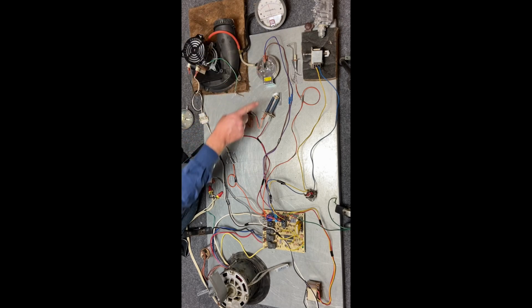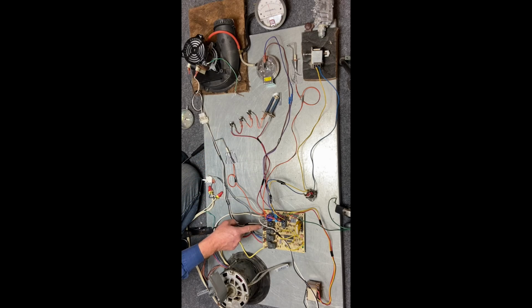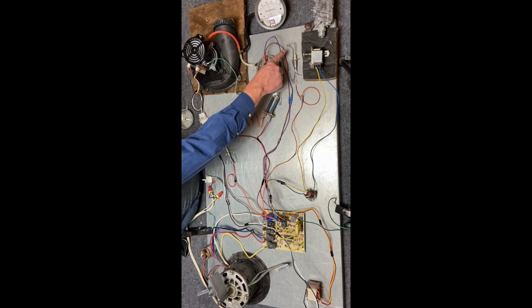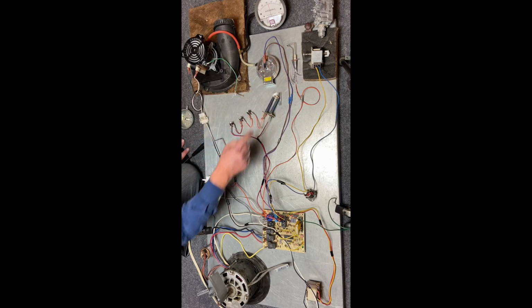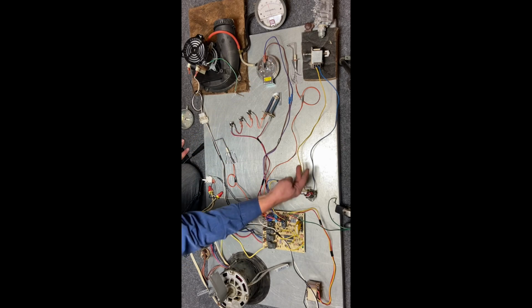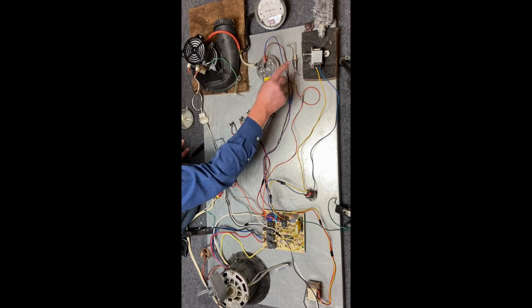This switch closes, sends 24 volts back to the IFC. It's going to let this run, the pre-purge of the heat exchanger, and then the IFC is going to energize this step-up transformer, which is going to have a little spark happening over here. And at the same time, it's going to send 24 volts through this switch to energize our electromagnet, and that's going to pull in. So if we wait shortly, it's going to start energizing. Here there's a spark happening, and you notice it's pulled in.